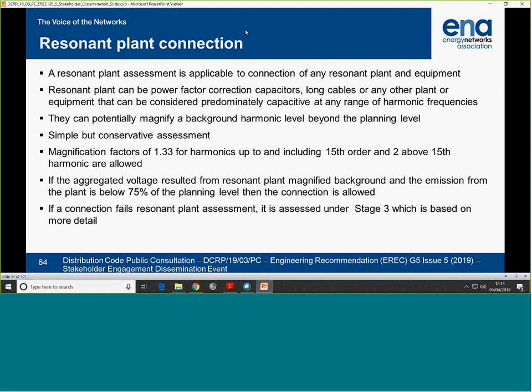So that's the benefit of having the contestable side of the design. You can worry about this, your headache for now. Yeah, if you know that you can have a cable with a resonance somewhere quite high, and you think, oh, it won't be a problem, then you go and stick a whacking great capacitor on the front end of it, and you know that you're going to bring that back in quite quickly. Just looking at it, you can say, oh, hang on a minute, I actually have a resonance situation here. The question is, a new connection or a tee connection changes that aspect of the network, the speed and source impedance. So you know that.